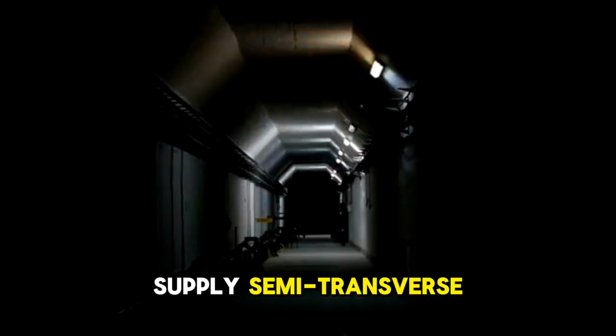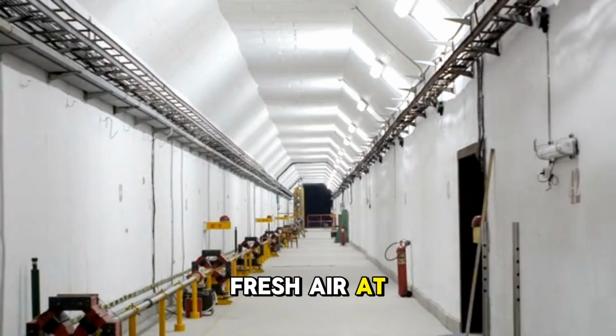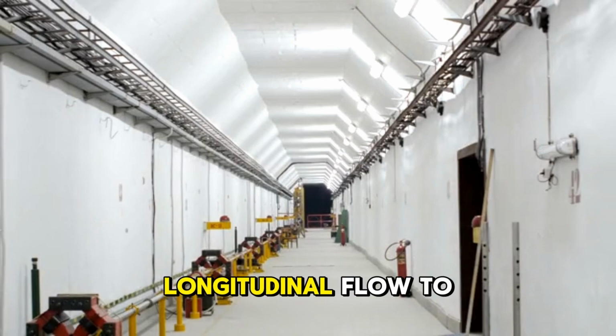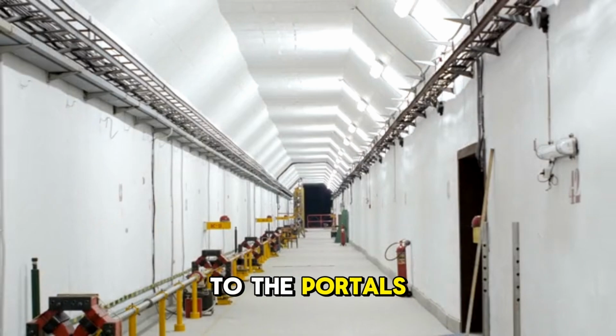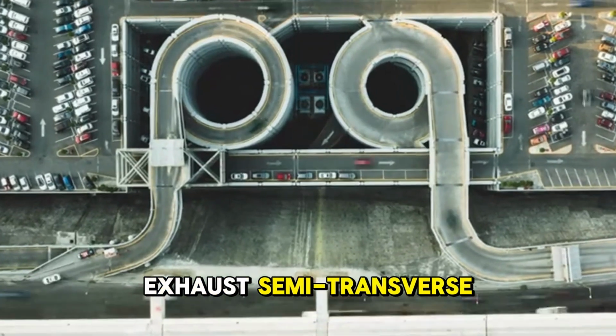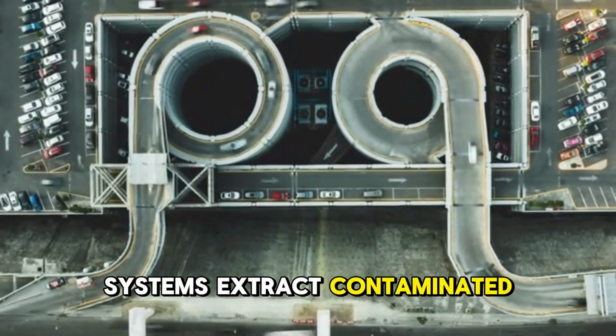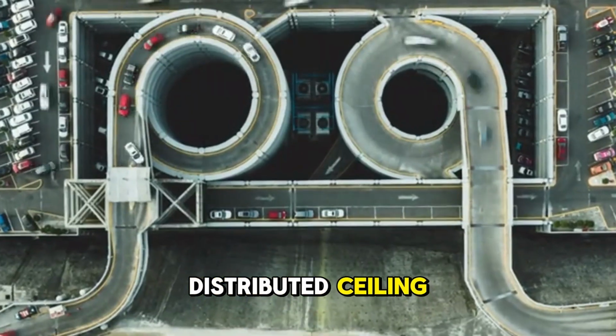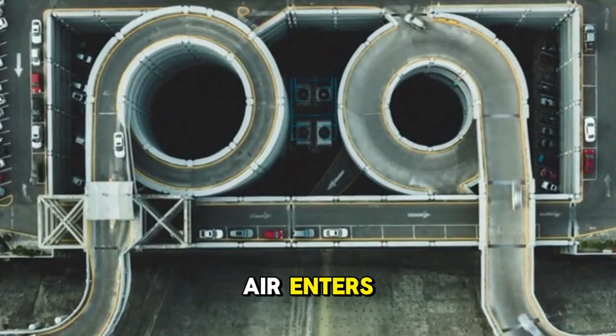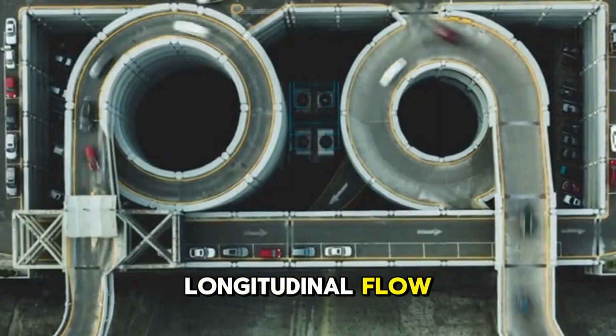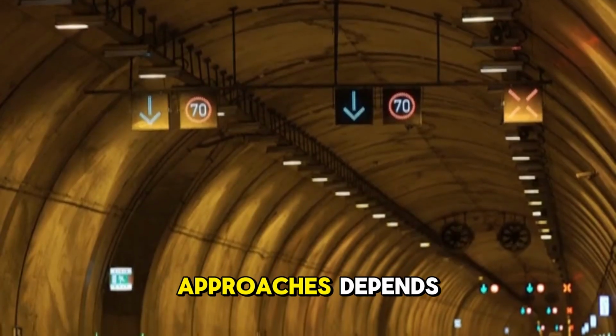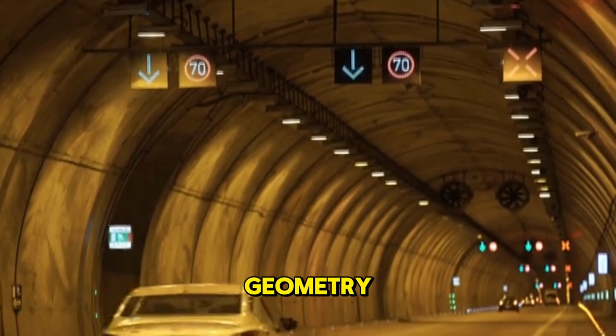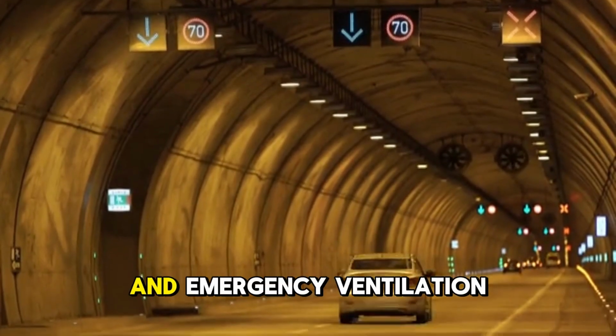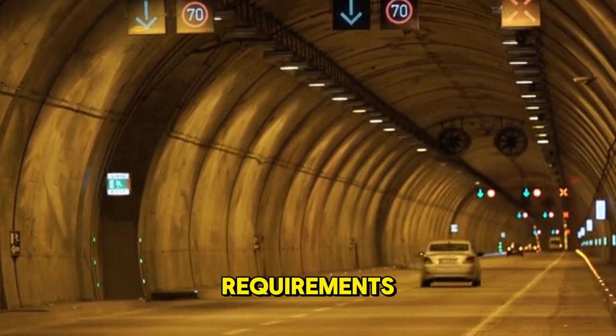Supply semi-transverse systems introduce fresh air at distributed points and rely on longitudinal flow to carry it and mixed contaminants to the portals. Exhaust semi-transverse systems extract contaminated air at distributed ceiling points, while fresh air enters through the portals by longitudinal flow. The choice between these approaches depends on the tunnel geometry, traffic characteristics, and emergency ventilation requirements.